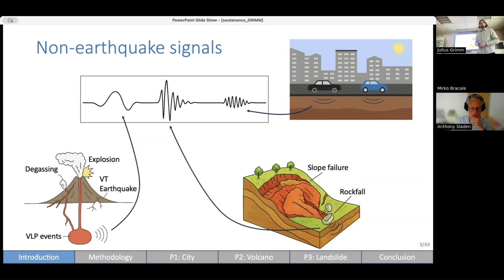During my thesis, I mostly worked with distributed acoustic sensing, and this is a new type of instrument, which was originally developed in the oil and gas industry in the early 2010s. But these days, it's increasingly used for monitoring natural seismicity. The setup of such a system is actually quite simple. You have a fiber optic cable, which acts as a sensing element, and to this fiber optic cable, we attach a so-called interrogator unit. This unit sends a laser pulse into the fiber, records backscattered light, and then computes the strain rate every few meters.